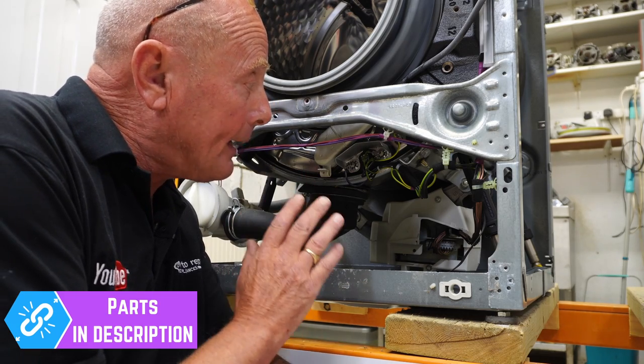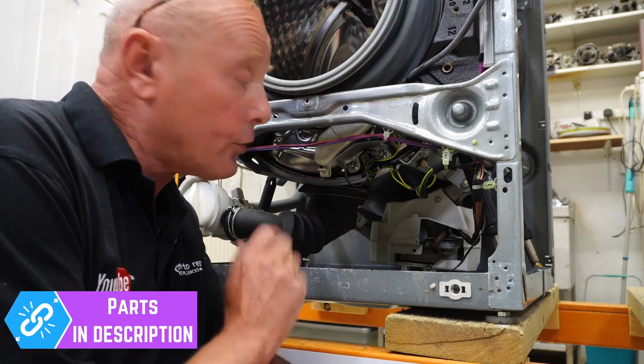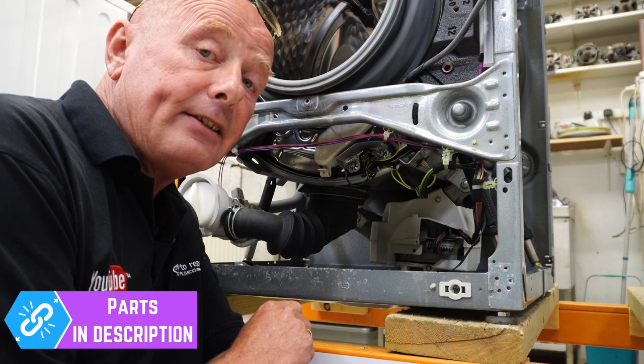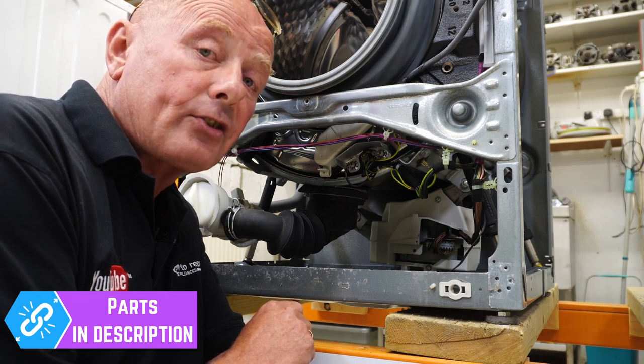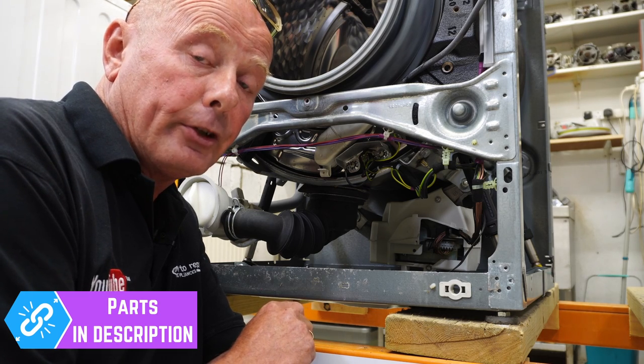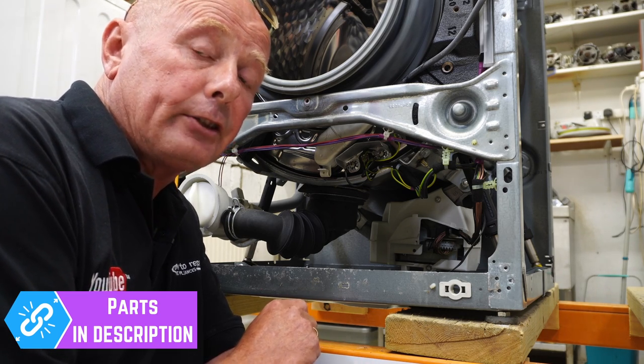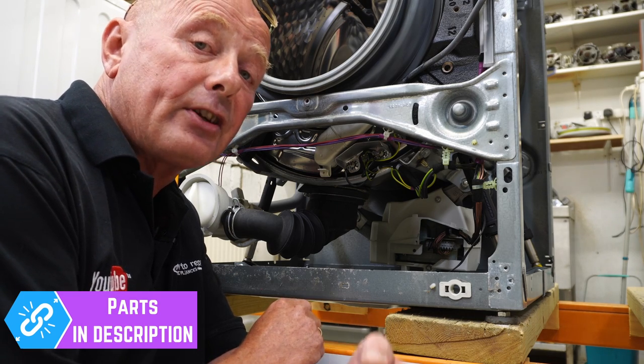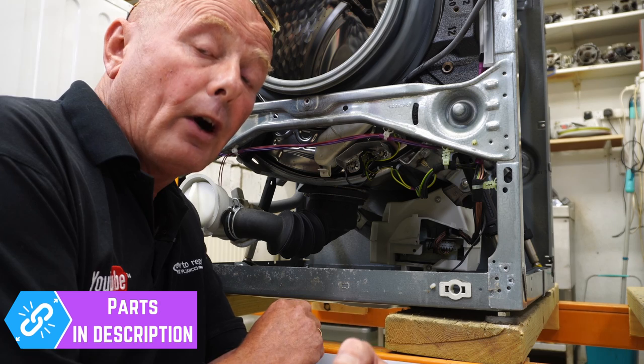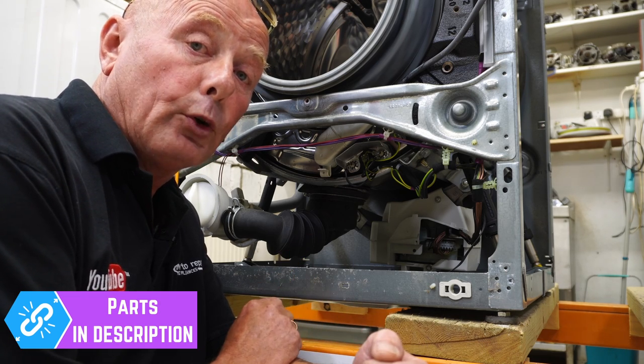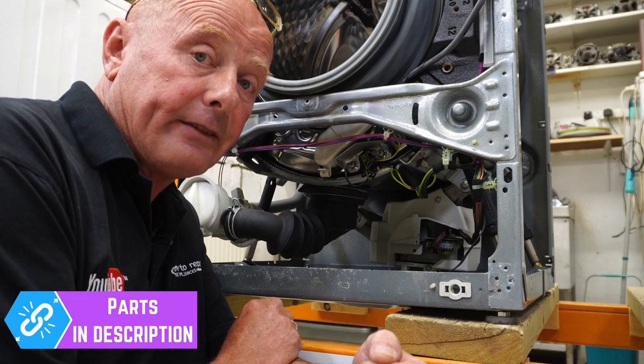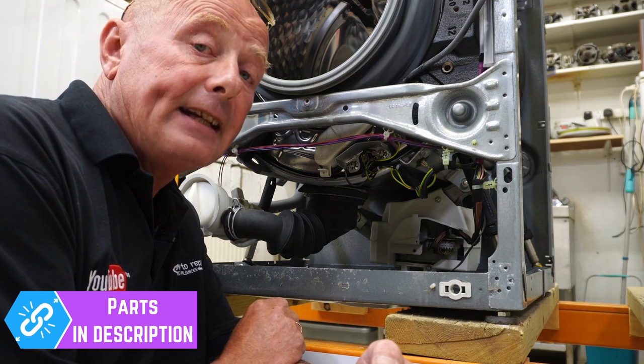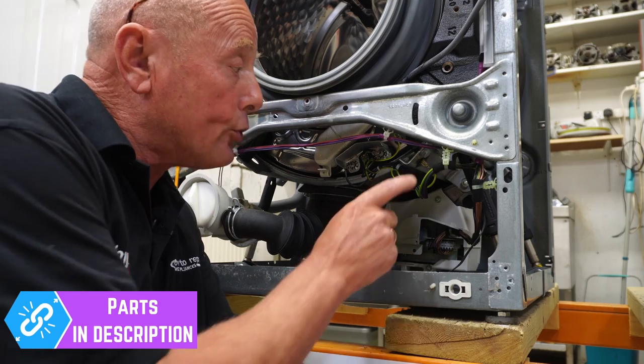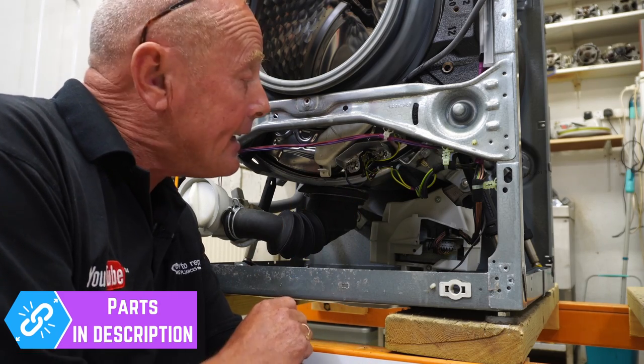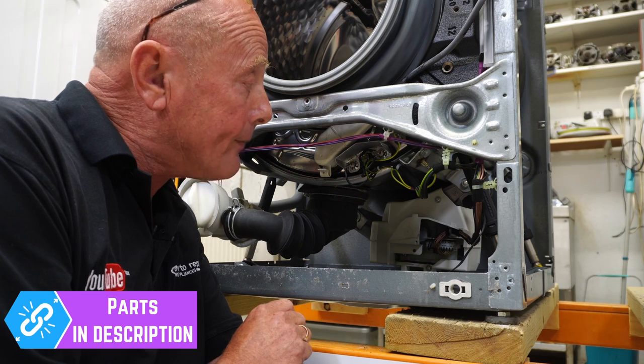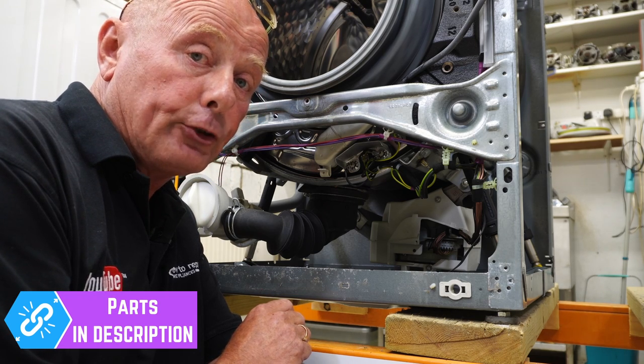Now, let me explain quickly how the NTC sensor works. At 25 degrees, the NTC sensor may have a set resistance value of, say, 4,800. As the temperature gets to 30, to 40, to 45 degrees, the resistance value will change. Therefore, at different temperatures, the circuit board knows what resistance it should be receiving, and therefore turns a relay on and off on the circuit board, which allows the power to come to the heating element. If you have a faulty sensor, you may have F1, F2 error codes appearing on your machine.